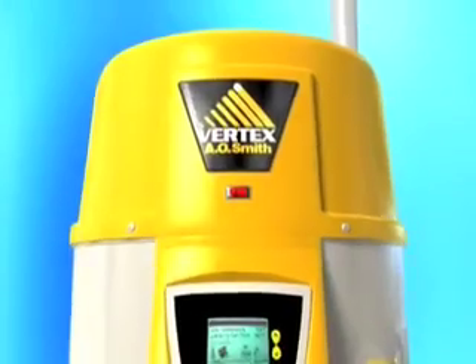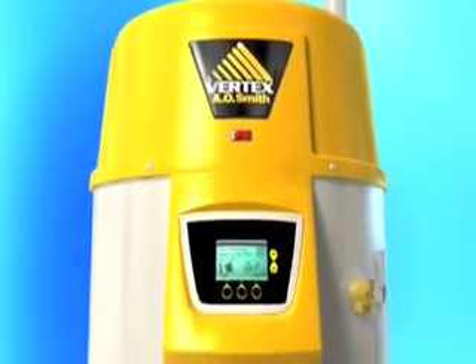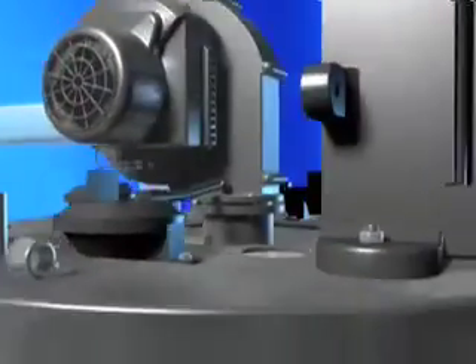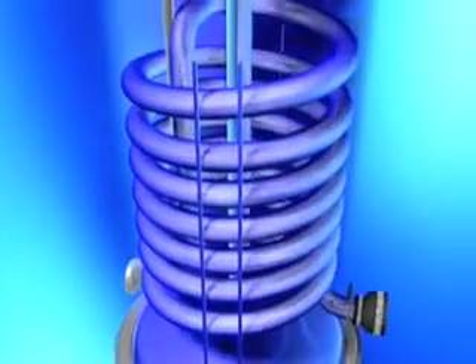The Vertex 100 achieves 96% thermal efficiency by employing a top-mounted downfire pre-mix burner similar to what is used in A.O. Smith's award-winning Cyclone commercial product family. Gases are forced straight down to the bottom of the tank, then up and back down through the helical coil for even greater heat transfer.